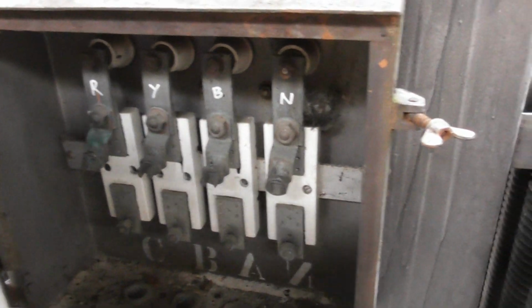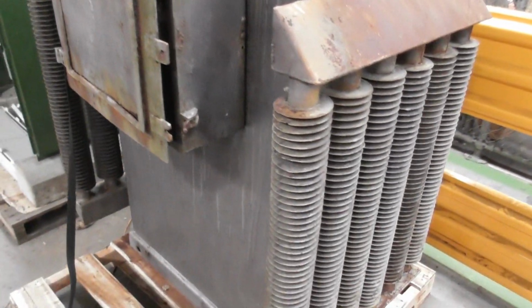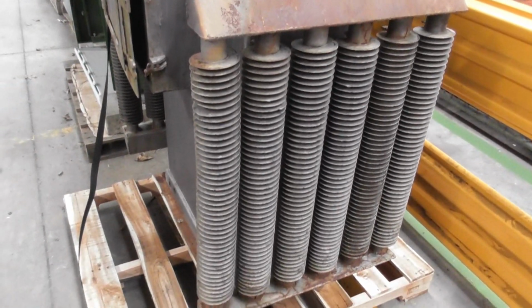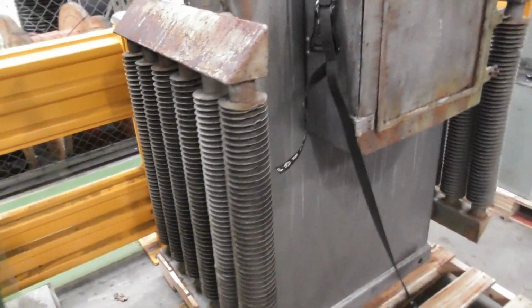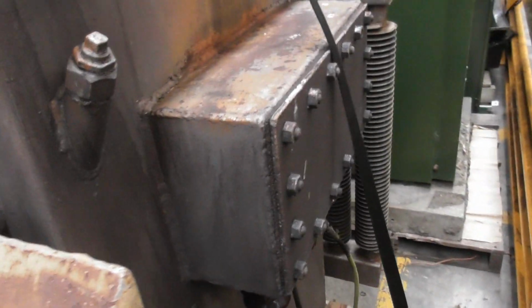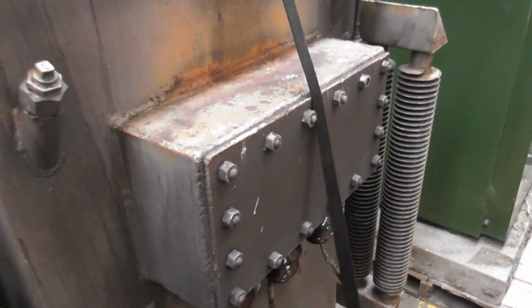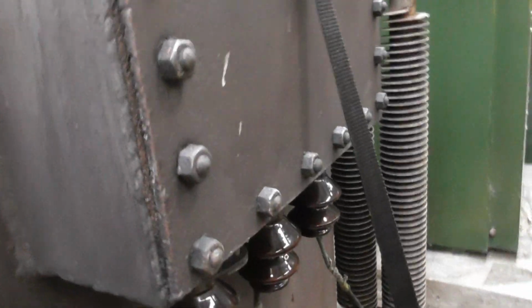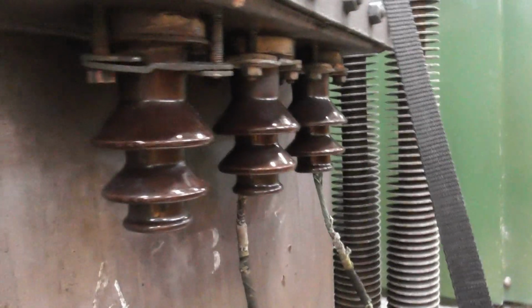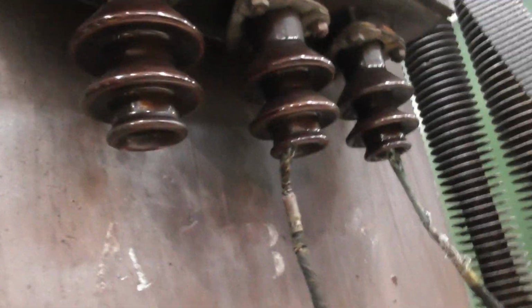CBA in. Like the radiator, so quite cool. And the other side radiator. And I'll have a look at the bushings on the other side. The HV bushings. They sit in this box here, the junction box. And we got underslung HV bushings on this device here. The cables are fixed.